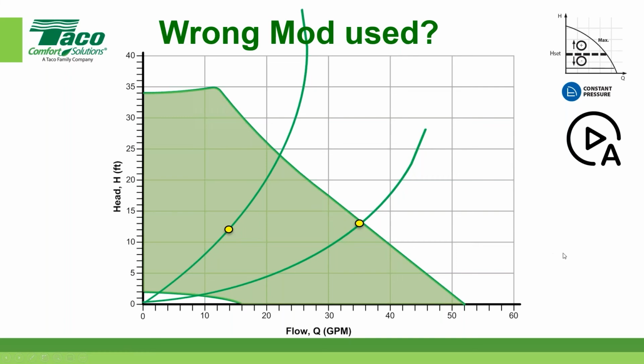Okay. Now, watch what happens if I should have put it in constant pressure, but I didn't. I left it in a fixed proportional mode or an automatic mode that was proportional pressure. Now remember what the bouncing ball does? It works its way down, works its way down, works its way down until you reach this point here. Now notice you no longer have the GPM that you needed for this zone. You can see the difference here. You no longer have the GPM and you no longer have the head. So you really wanted to be up here like this. This drops you back down here and here.